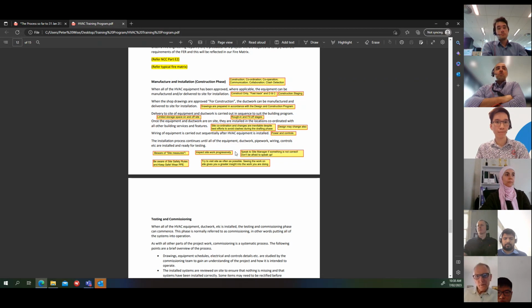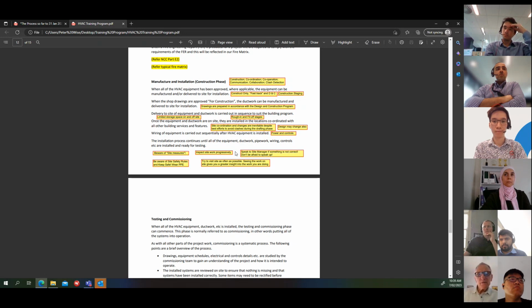It's a good question, because this happens quite a bit, where certain zones, say in an office building, perimeter zones may not be achieving the design conditions. Maybe during the calculation process they got the angle of the building wrong, and the solar load is greater than expected, or maybe it turns out the glass is the wrong glass. You need to look through all that and find the root cause of the problem. It's quite common to not achieve the design conditions for whatever reason, and you need to understand the reason, and then the responsible person has to fix it.